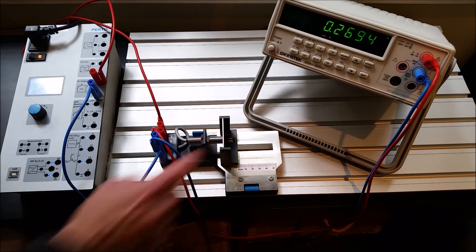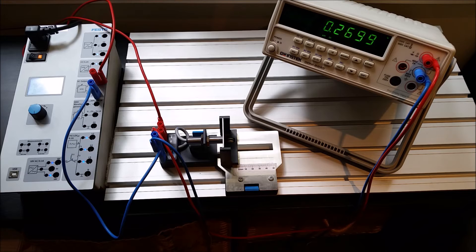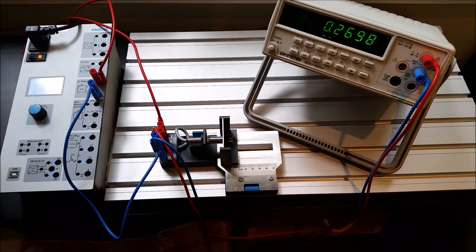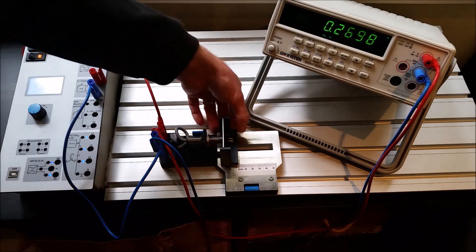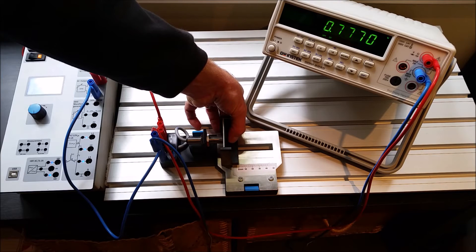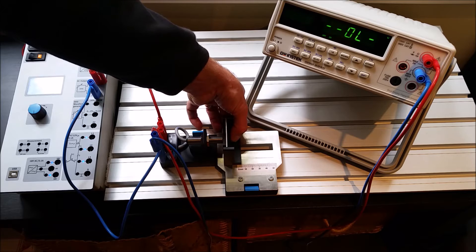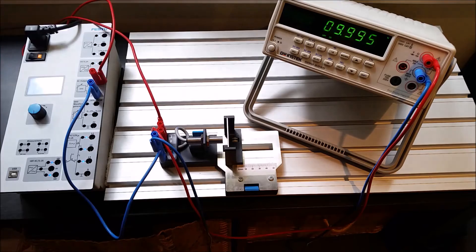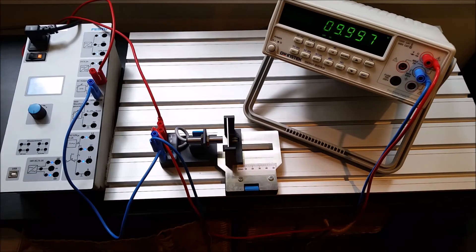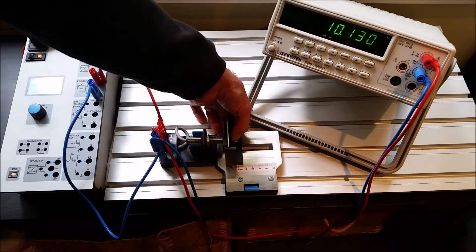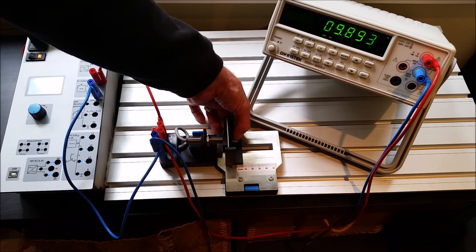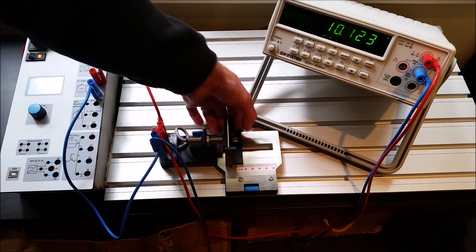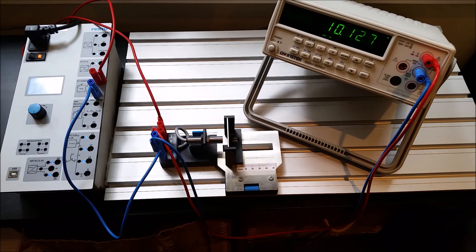The target distance, nominal sensing distance of this guy is 6 mils. So we're going to back this up 6 mils. And this is going to go from 0. You can see that the voltage is slowly climbing. And when we get to 6 mils, then there is 10 volts. So we've got 0 to 10 volts going from 0 to 6 mils.